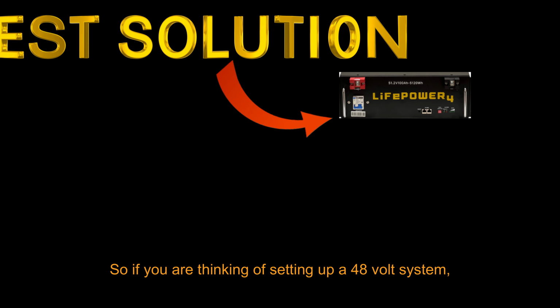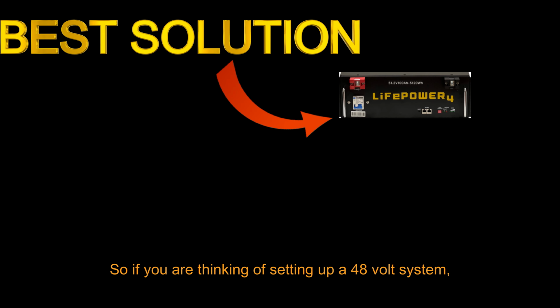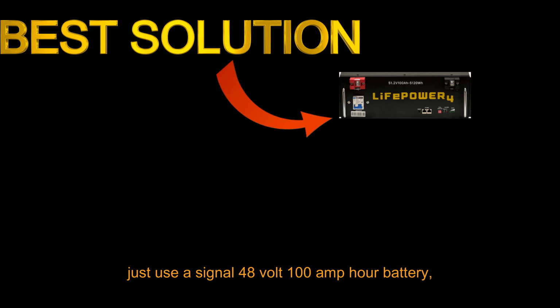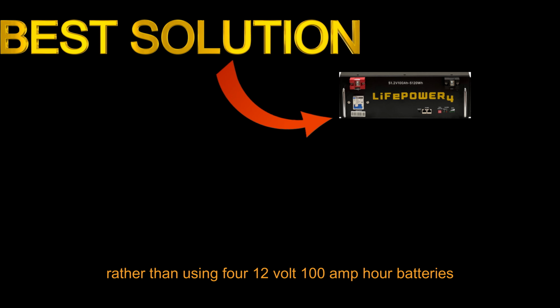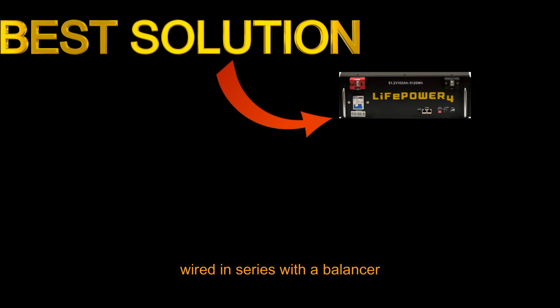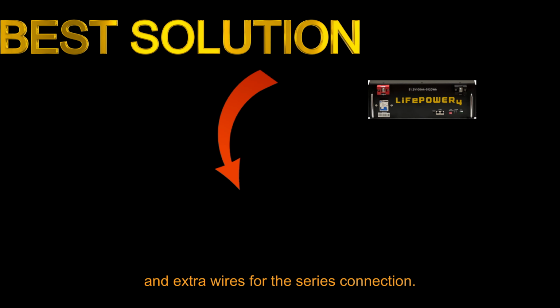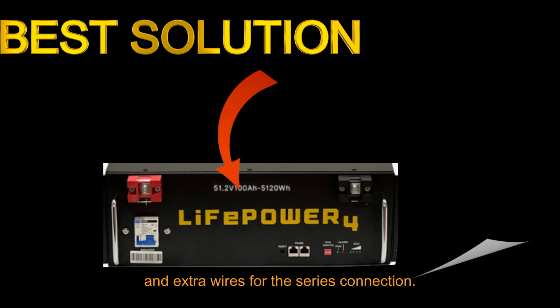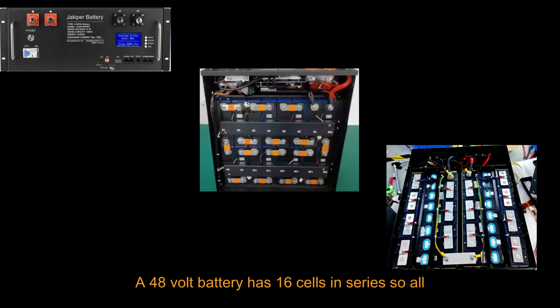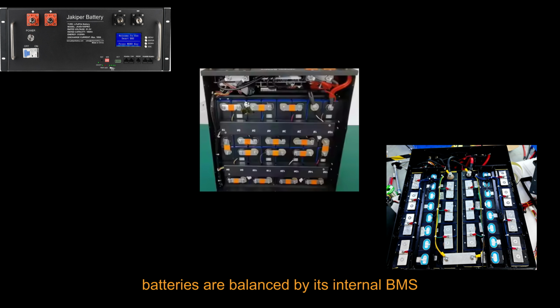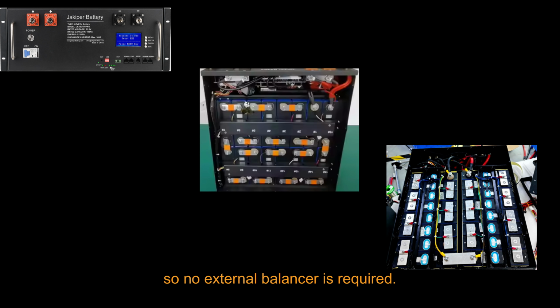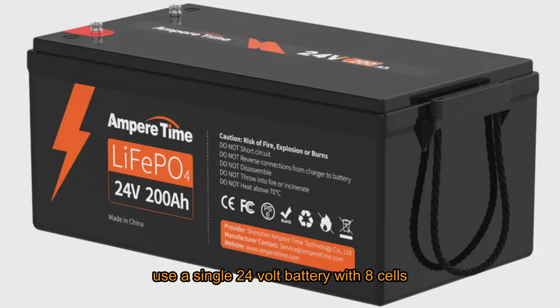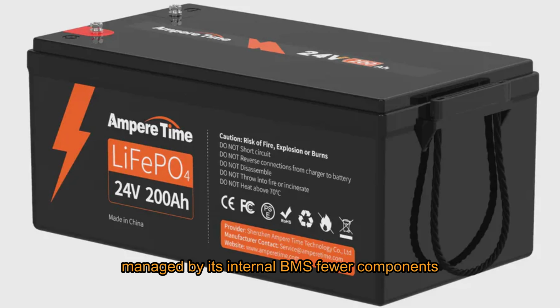So if you were thinking of setting up a 48-volt system, just use a single 48-volt 100 amp-hour battery rather than using four 12-volt 100 amp-hour batteries wired in series with a balancer and extra wires for the series connection. A 48-volt battery has 16 cells in series, so all cells are balanced by its internal BMS, and no external balancer is required. This is the same logic when using a 24-volt system: use a single 24-volt battery with 8 cells managed by its internal BMS—fewer components, fewer headaches.